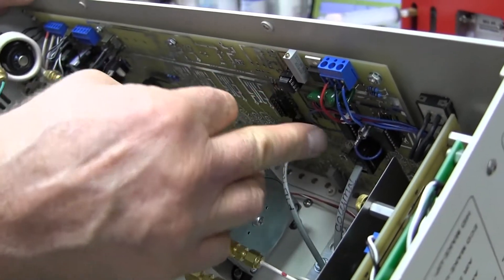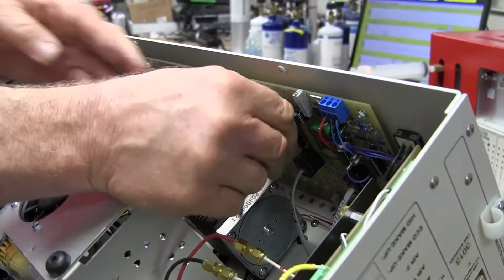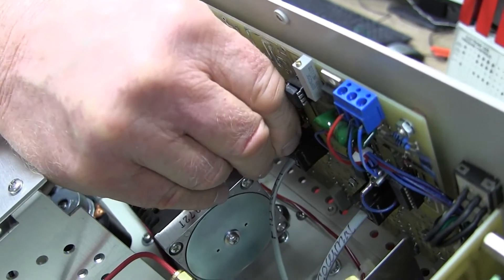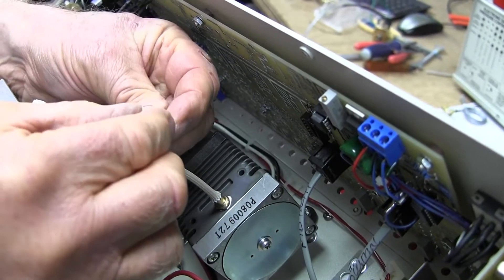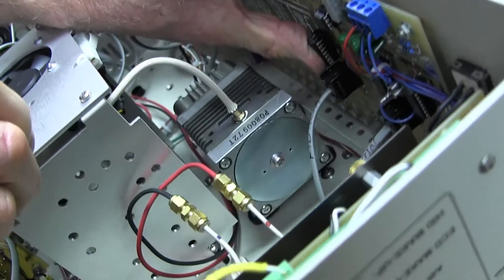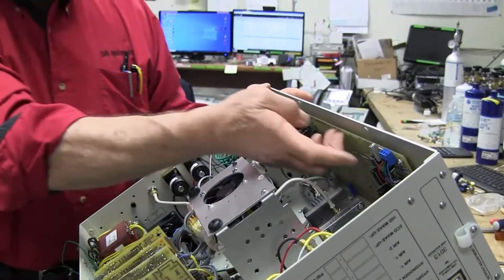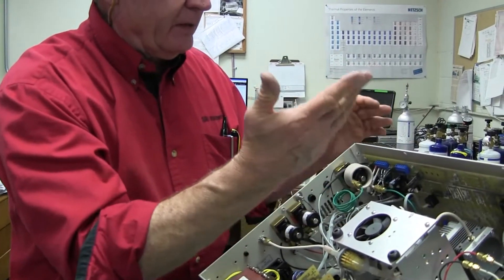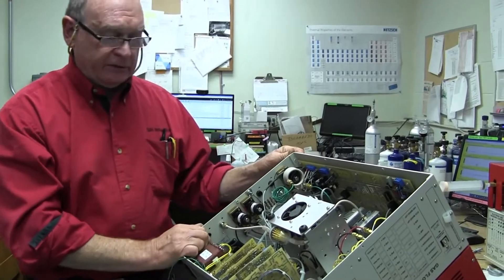So all of these chips here are identical. So if you couldn't remember which way was which, you could just look and see which way its neighbor was pointing, and you'd know which way to put it in. So when you put it in, you have to have a degree in massage because you've got to get all those little legs into the socket. If any of the legs are not going in, they're missing, then it's not going to work. So you have to make sure that you've got good light, you can see. And then before you really push in, you've got to make sure that you do actually have everything in, the little legs are in the socket before you give it the final little push to go in. So we give you an extra one of these chips with the GC. It's in the little plastic parts box under the red lid, and they're very common chips. You can probably find them on Amazon for 50 cents each, so they're not hard to find. And if those chips go bad, then it can also cause this red light to light.